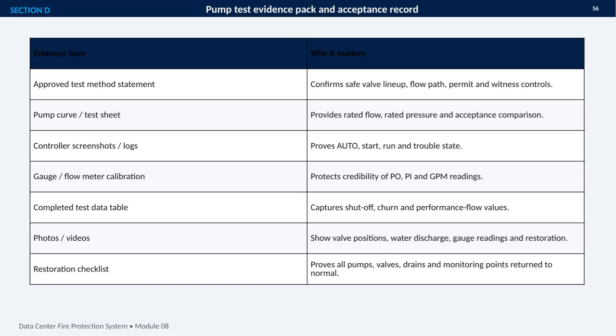This section focuses on the pump test evidence pack and the acceptance record. The goal is not simply to perform the test, but to create a complete, traceable record showing what was tested, how it was tested, and whether the results are acceptable. The approved test method statement establishes the controls up front, including the valve lineup, flow path, permits, and required witnesses. The pump curve or test sheet provides the basis for comparing rated flow and pressure with actual performance. Controller screenshots and logs verify the key operating states: auto, start, run, and trouble. Calibration records for gauges and flow meters protect the credibility of the pressure and flow readings.